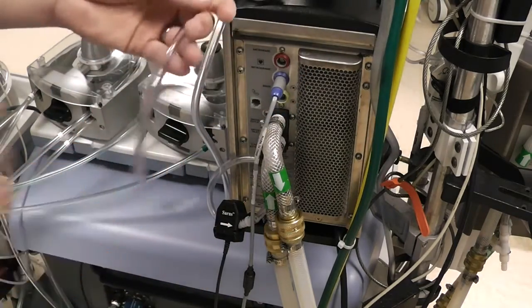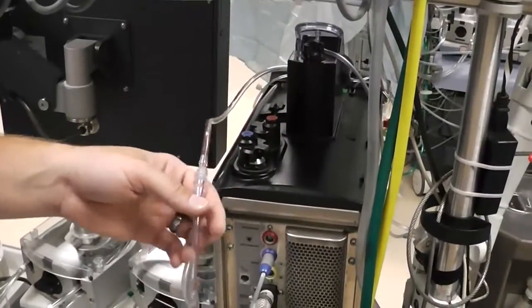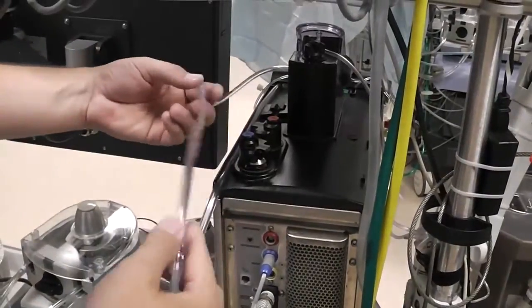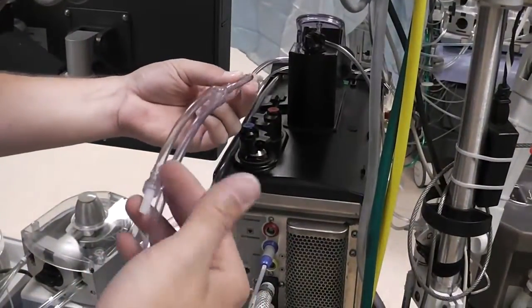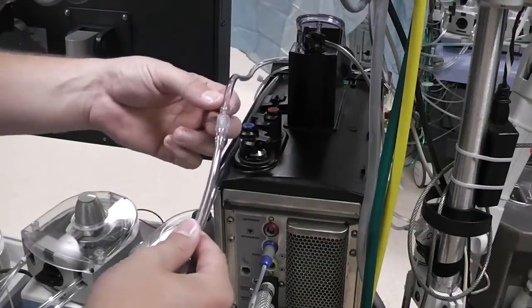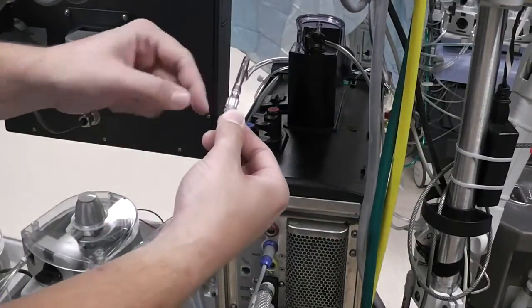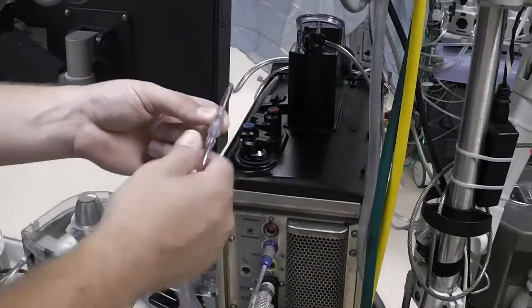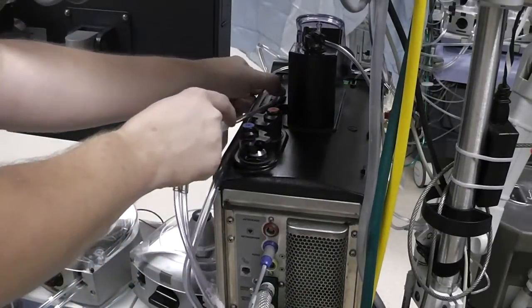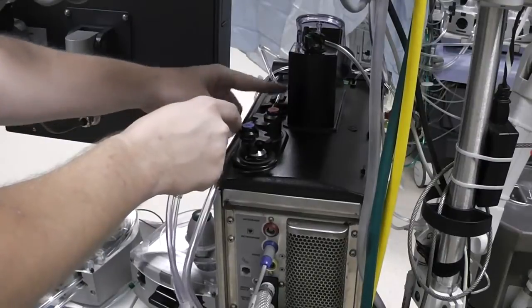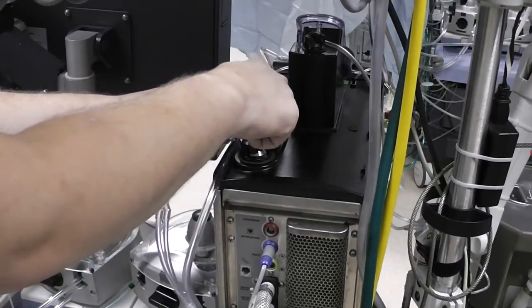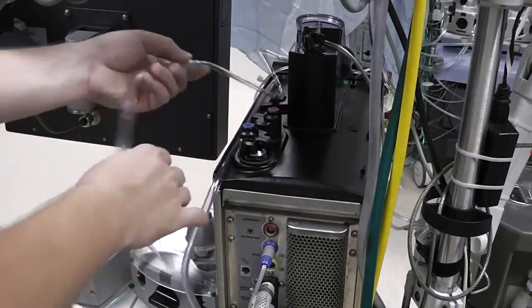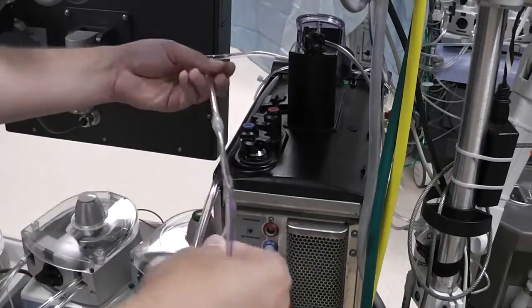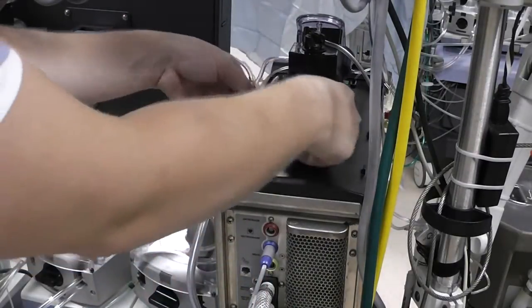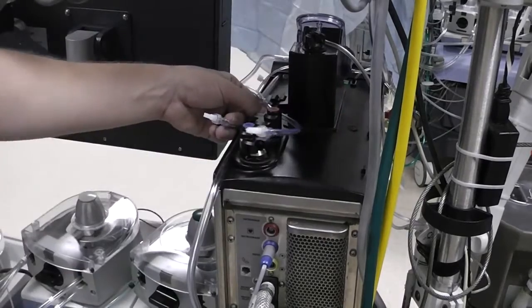Now for these connections, this is with retrograde attached. So if you have just antegrade, this is going to end here. This tail piece isn't going to be on the line, and you're just going to seat this in the air detector here and run it through the antegrade clamp. But as it is, we're going to seat the red, push down on this.